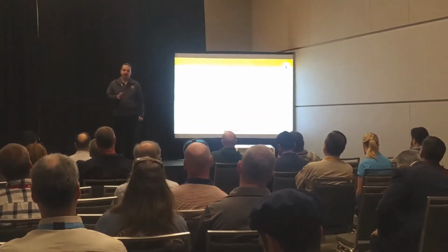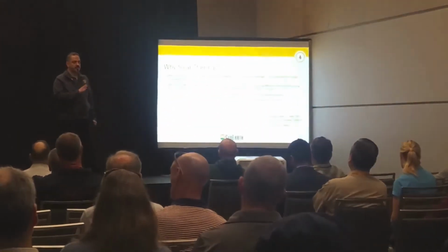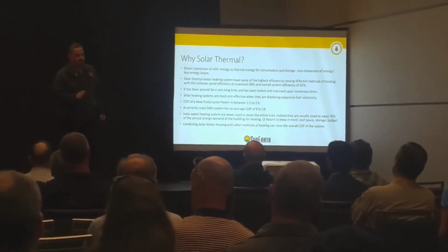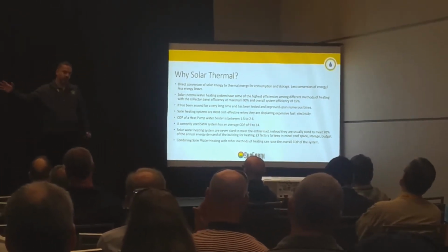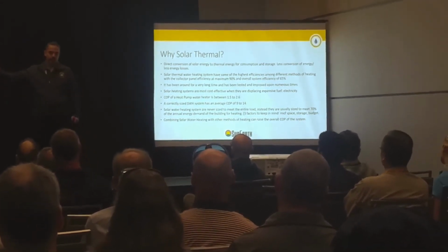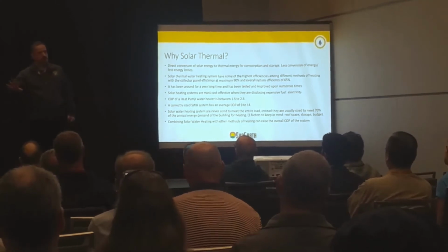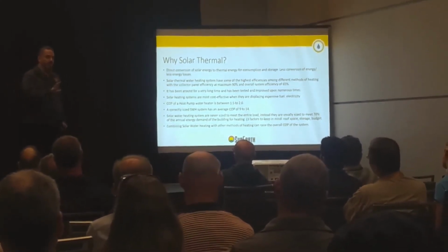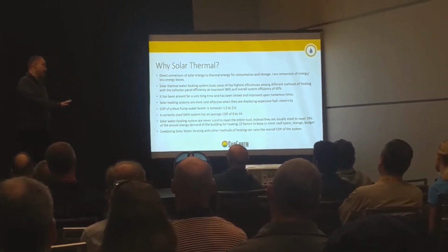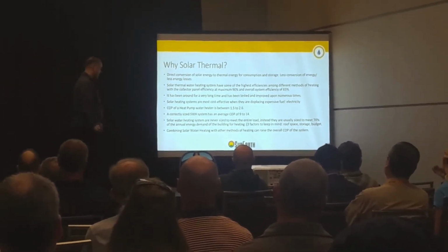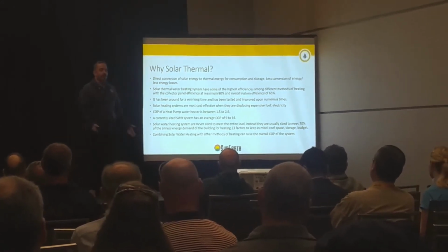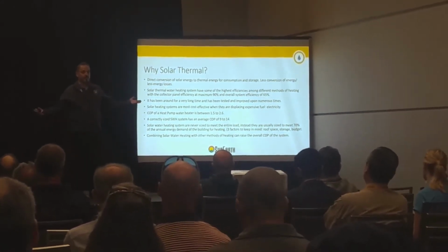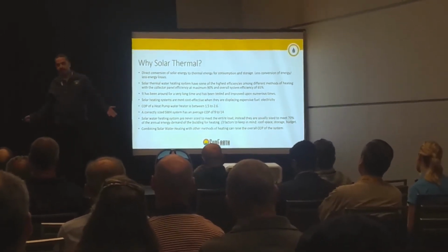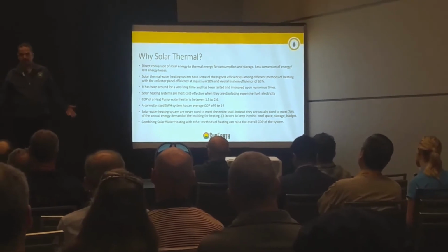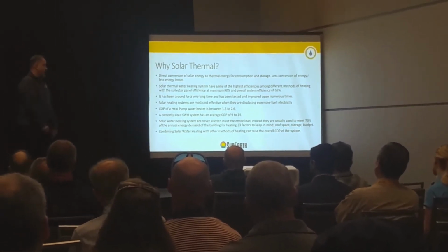But when we talk about solar thermal, there are several things that you need to keep in mind. First of all, when designing a solar thermal system, you never ever design it to meet your entire load. You figure out what your load is, you design your secondary heater based on your entire load, and your solar thermal system is designed to meet a percentage of that load. So there are three factors that you keep in mind when you're designing the system. How much roof space you have available, that's the first one. If you need 2,000 square feet of collector and you only have 500 feet of roof space, that's the first limitation. We move on to storage.